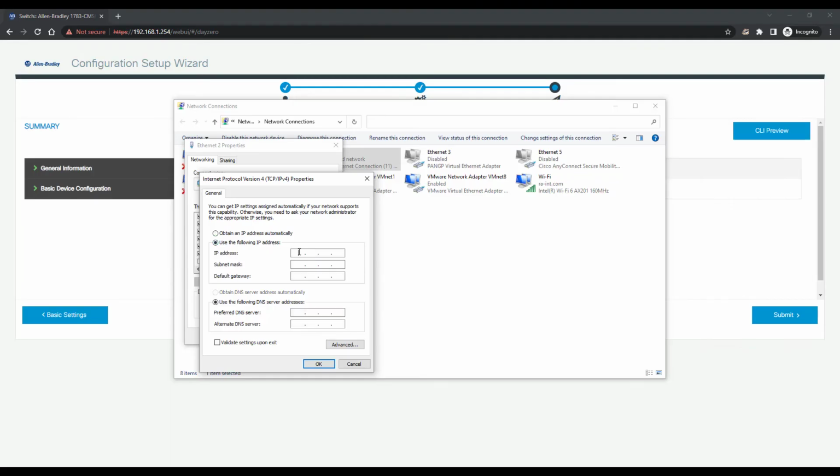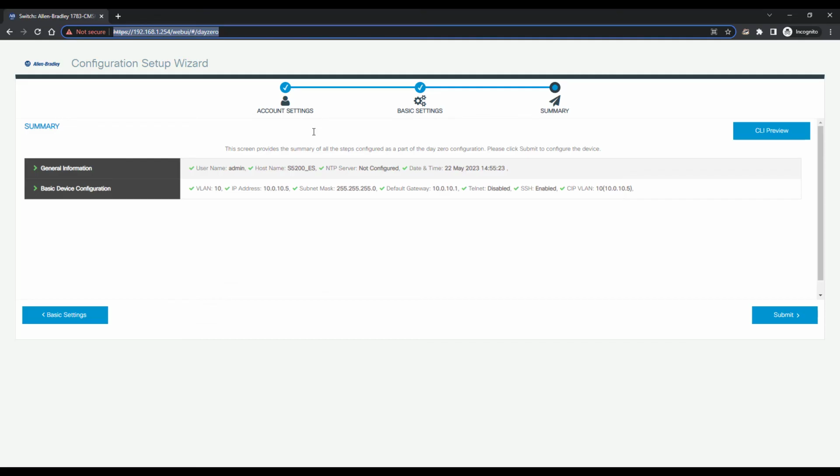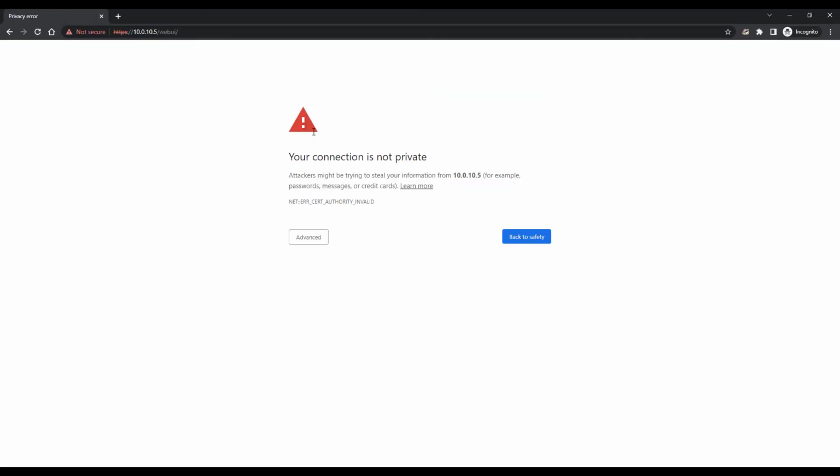The switch will initialize its configuration for typical Ethernet IP protocols by running the global macro, which is a benefit of the Express Setup process. The switch can now be connected to the network and configured further by accessing the web UI, or it can be connected to directly using the newly assigned IP address. If direct connection is required, you will need to change your workstation IP settings in order to connect since the switch is no longer using the default IP address.